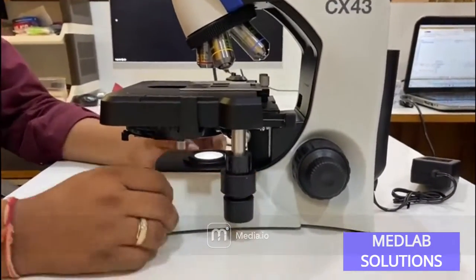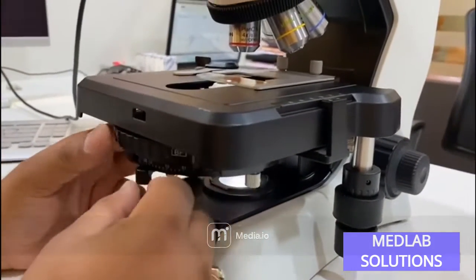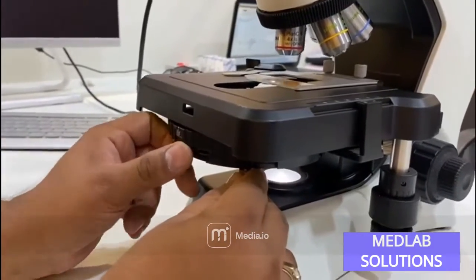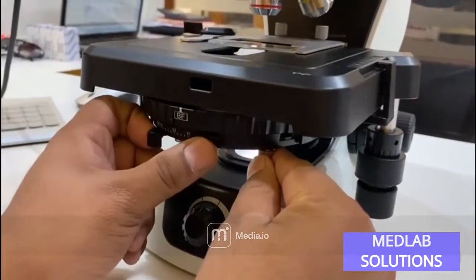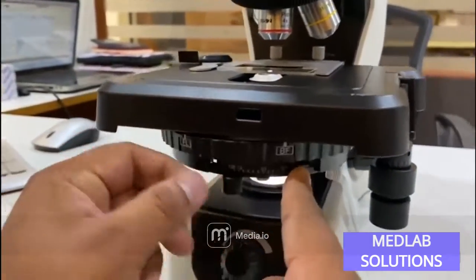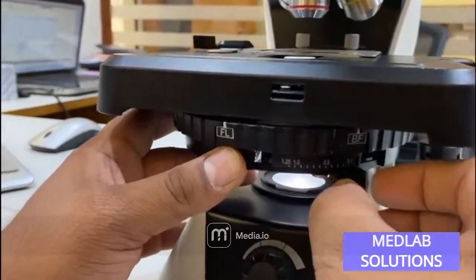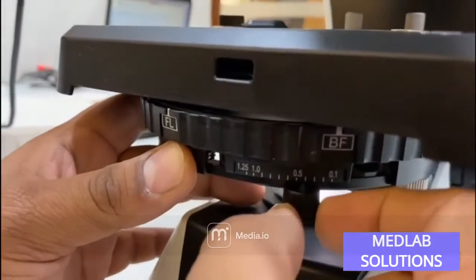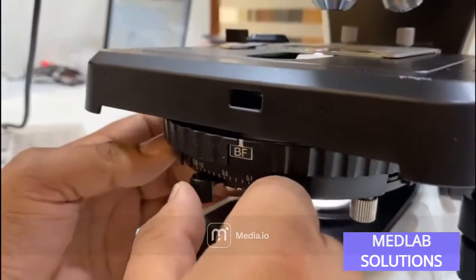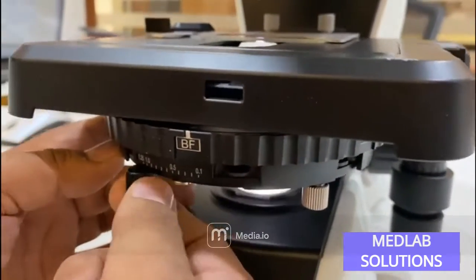Ergonomically, you also get a turret position to increase or decrease the diaphragm directly overhead. As you can see, there is a turret movement to choose the diaphragm setting as per your requirement — 0.1, 0.5, 1.0, and 1.25. This allows you to adjust contrast in bright field mode using the diaphragm.